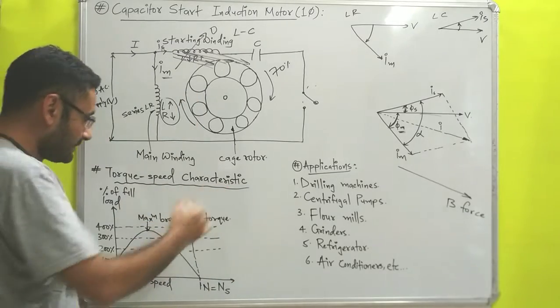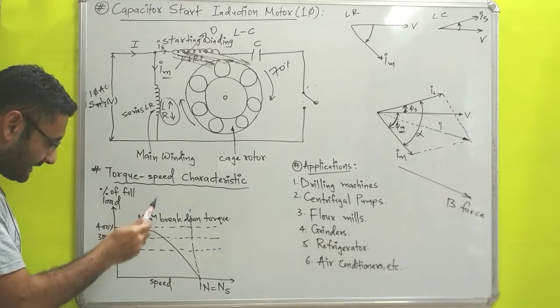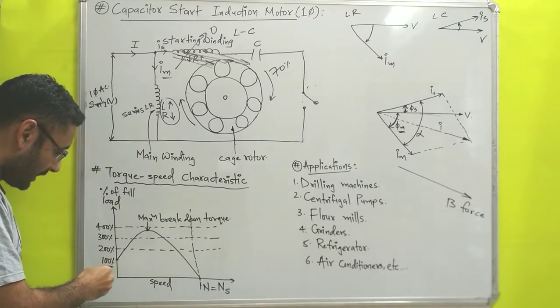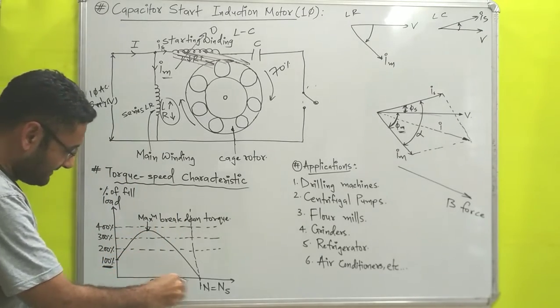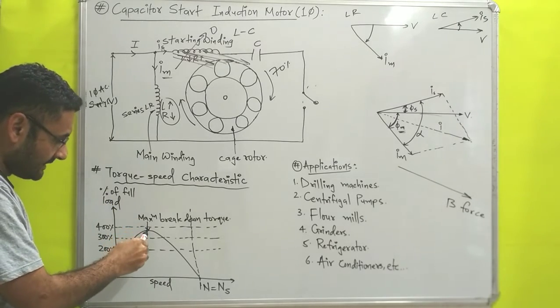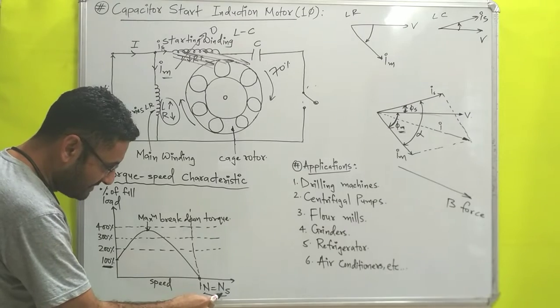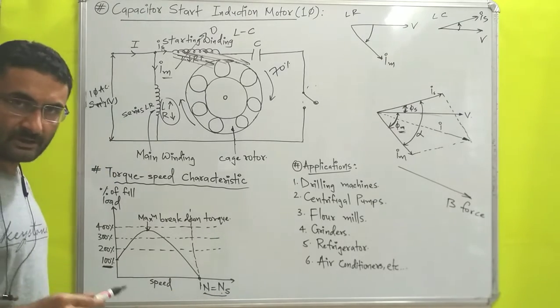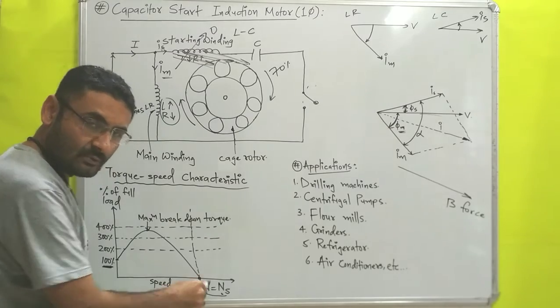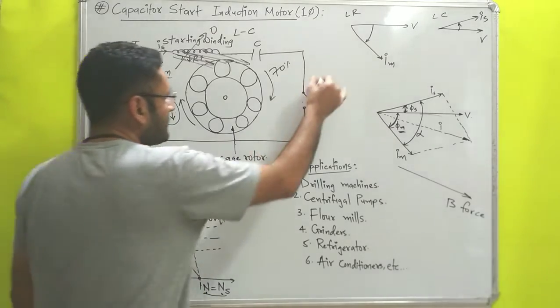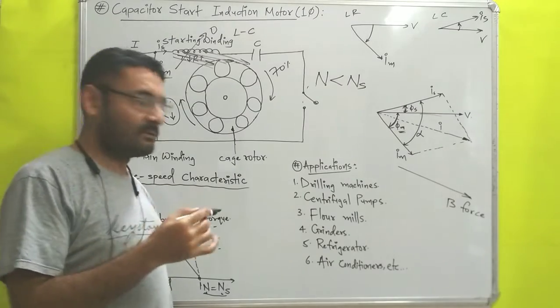Now for the torque-speed characteristics: the horizontal axis represents speed and the vertical axis represents the percentage of full load torque. To start this motor, you need to supply 100% of the full load torque. As speed increases, torque also increases up to its maximum breakdown torque, after which torque decreases and becomes zero when synchronous speed equals the actual rotor speed. Generally, the actual rotor speed is less than the synchronous speed.